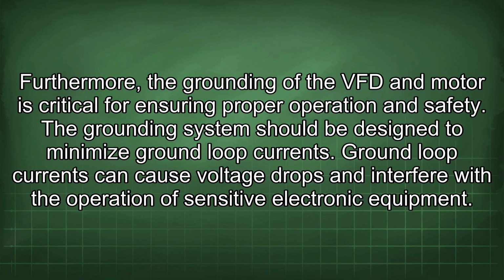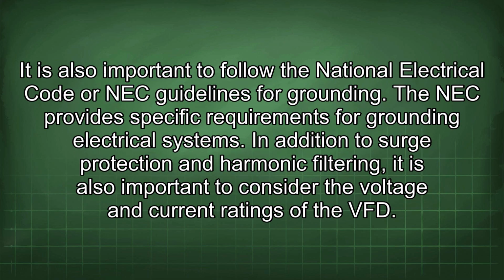Furthermore, the grounding of the VFD and motor is critical for ensuring proper operation and safety. The grounding system should be designed to minimize ground loop currents. Ground loop currents can cause voltage drops and interfere with the operation of sensitive electronic equipment. It is also important to follow the National Electrical Code or NEC guidelines for grounding. The NEC provides specific requirements for grounding electrical systems.